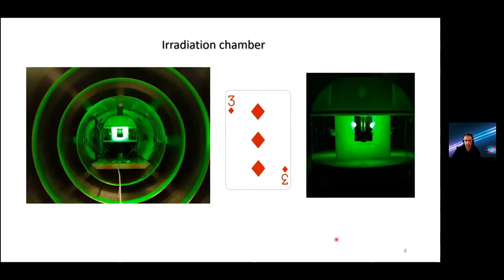It appears that irradiating sample outside NMR magnet makes a huge difference because you can do it really efficiently if compared to experiments where you do CIDNP directly in high field. This is because you can really put a lot of LEDs around your sample and you can increase concentrations. Here we designed some holder which contains also Helmholtz coil, it is placed in the magnetic shield, and the high power LEDs which are in fact very cheap, and we have some airflow to control the temperature.